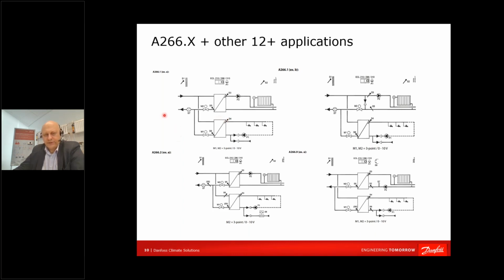Some ask, which sensors are mandatory? Mandatory sensors will always be on the supply line, for domestic hot water and heating; these are a must. Of course, outdoor temperature sensors should be in the business. You might think over whether you should include the sensor for room temperature measurement. Maybe yes, maybe no. We will speak about how the room sensor works. Some applications won't work well if you do not attach the room or outdoor sensor.